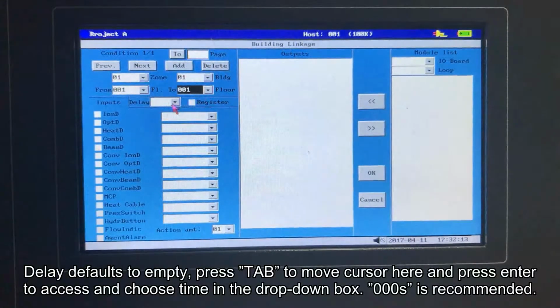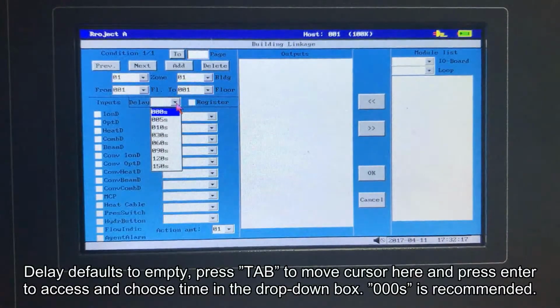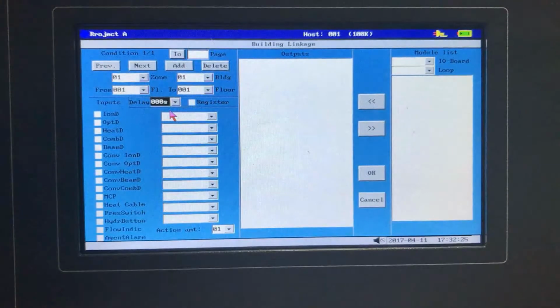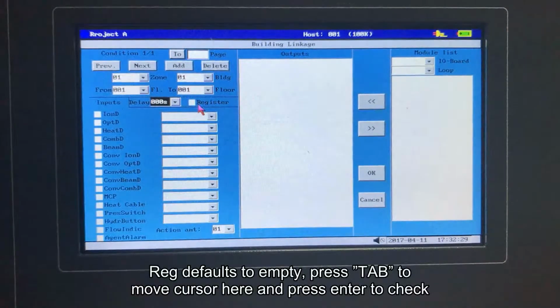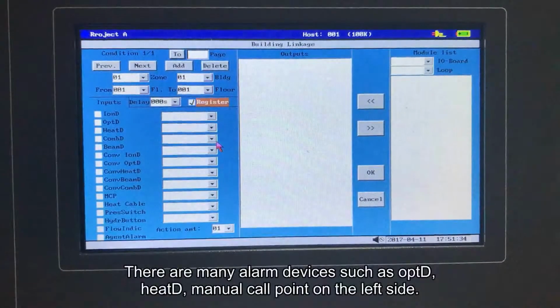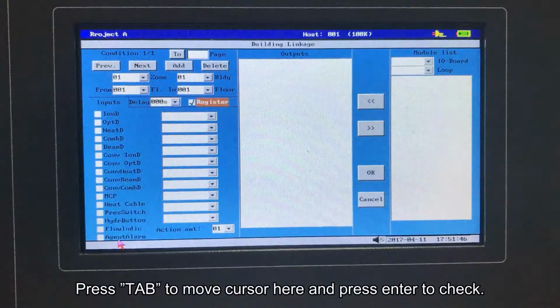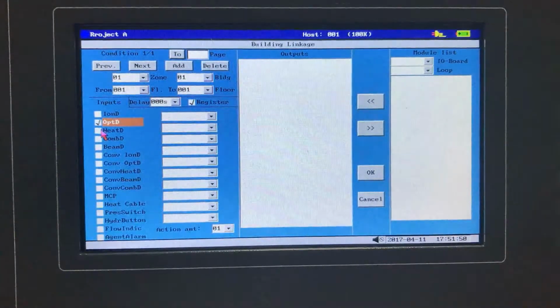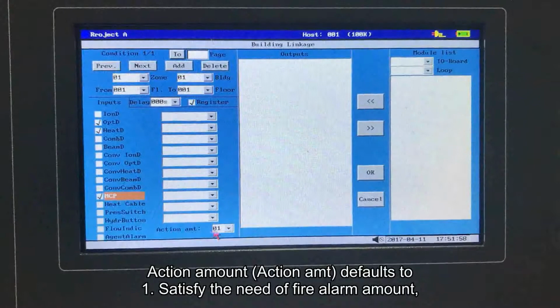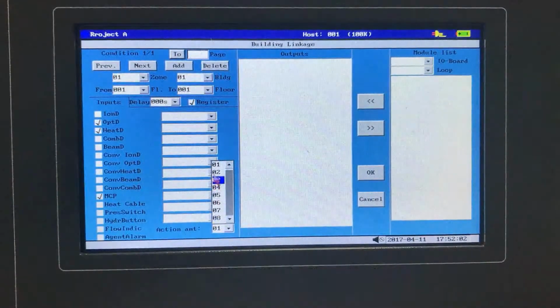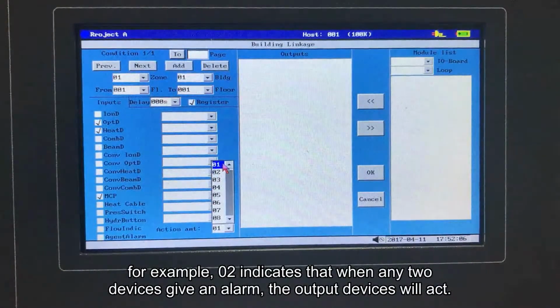Delay defaults to empty. Press Tab to move the cursor here and press Enter to access and choose the time in the drop-down box. 0 delay is recommended. REG defaults to empty. Press Tab to move the cursor here and press Enter to check. There are many alarm devices such as OPT-D, HEAT-D, and manual call point on the left side. Press Tab to move the cursor here and press Enter to check. Action amount defaults to 1. Satisfy the need of fire alarm amount. For example, 02 indicates that when any 2 devices give an alarm, the output devices will act.